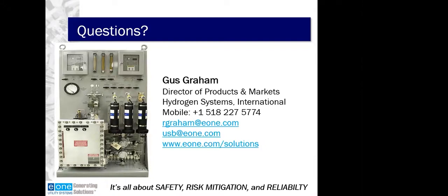Some more questions coming in. How can we link the dew point gauge readings with H2 accuracy of display? So dew point has a very small effect on purity level. It would take a very, very high dew point to even begin to approach an effect on the purity reading of the gas. I don't have the exact values in front of me. There was a study conducted to show at what dew point you even begin to affect purity. I can take that question down, Rach. We can do a little research and try to get the answer back to whoever provided the question.